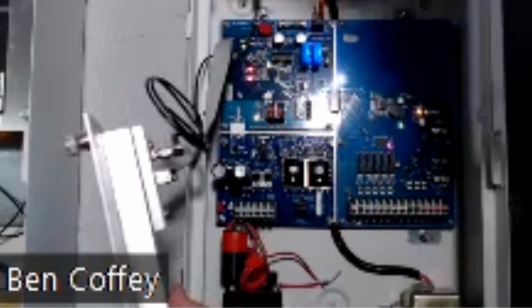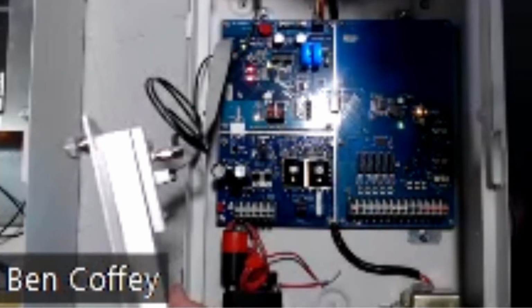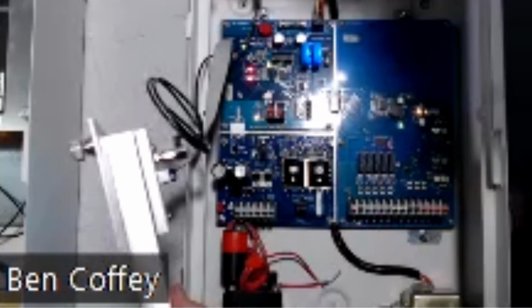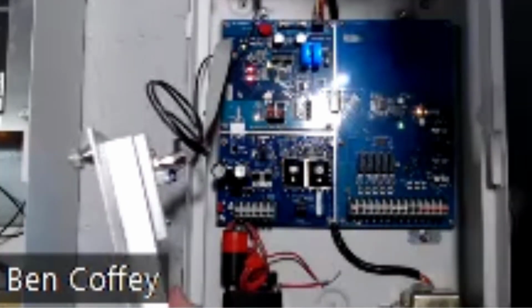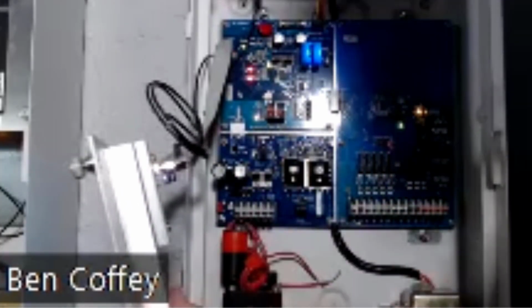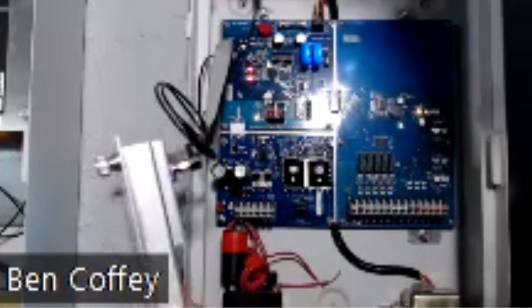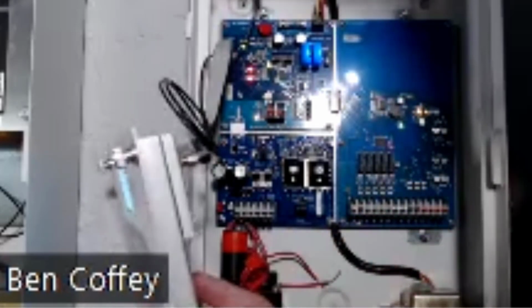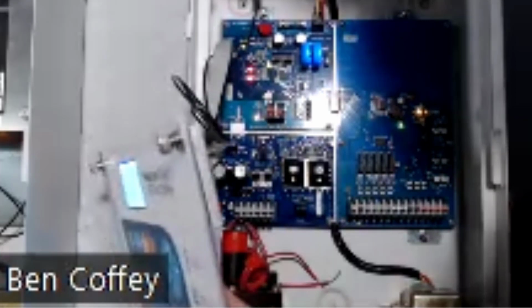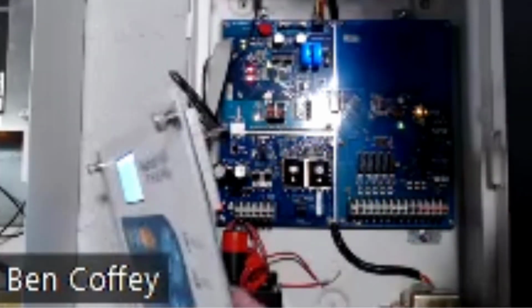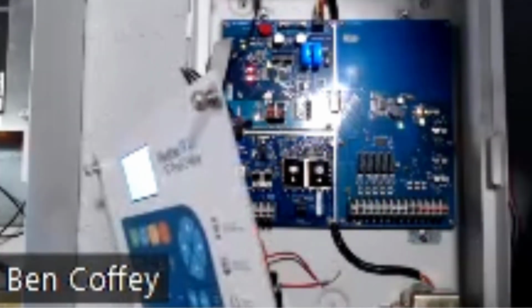Absolutely. And I would highlight that the system is capable of running 4 master valve and flow sensor setups. Direct wire is an option, so is adding that to the 2-wire path. So these ports would only be used if you direct wire those components, but if you add them to the 2-wire path, each one will require its own decoder. So with WeatherTRAK, that's an option. You can go either way, and you can even mix and match.